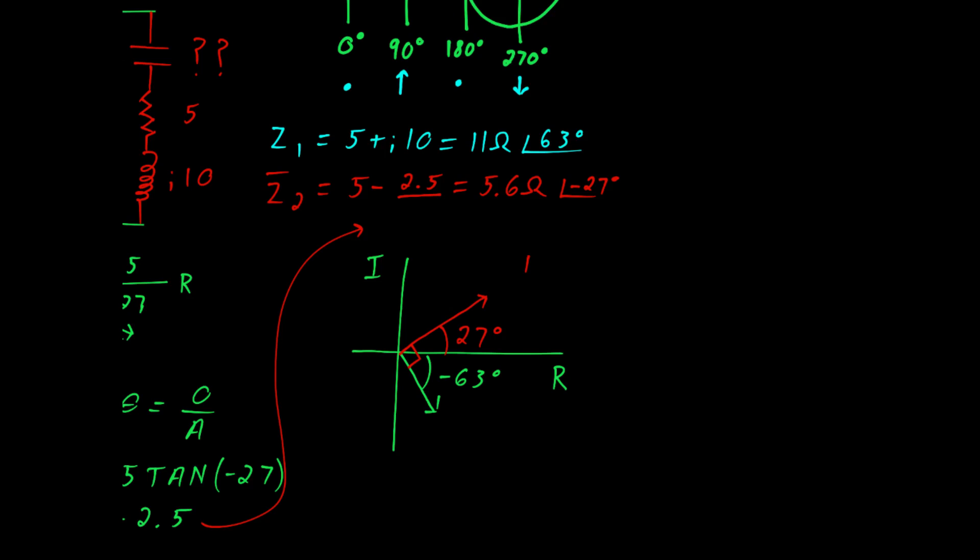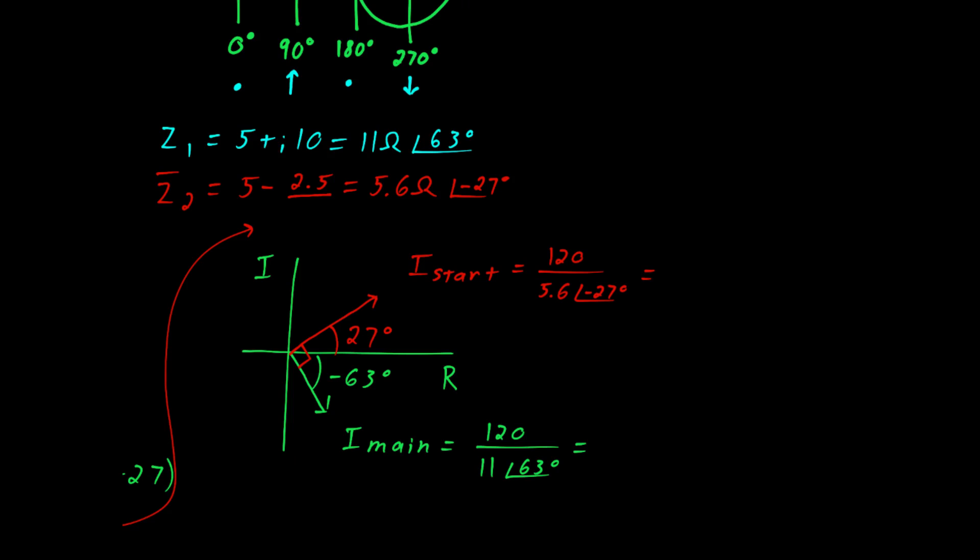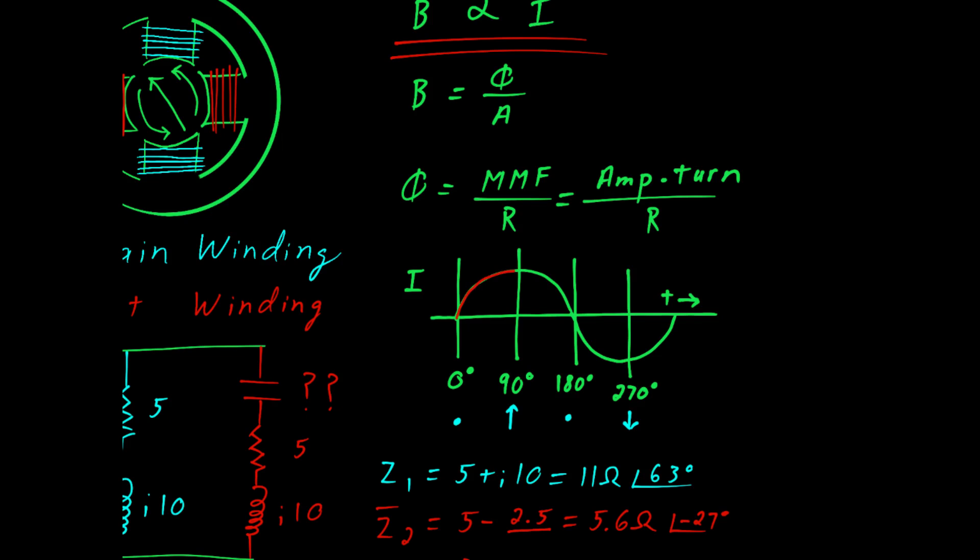We can now compute the current in each branch of the machine. In the main winding we have 11 amps at a phase angle of negative 63 degrees. In the start winding we have 21 amps at an angle of 27 degrees. To our original time domain plot we can add the current for the start winding and for the main winding. My apologies folks I got the colors backwards here. But you can see they are offset from each other by 90 electrical degrees with the start winding having a greater amplitude.